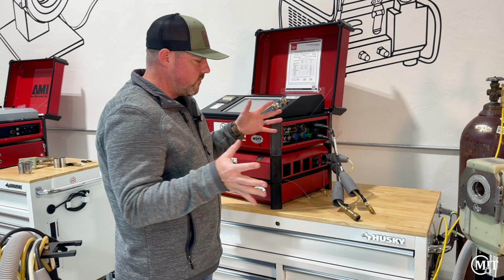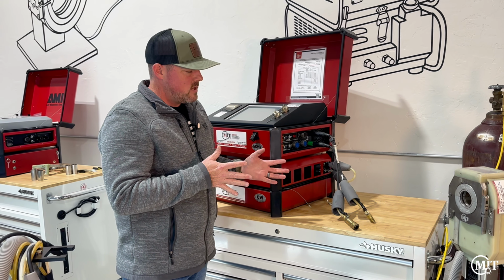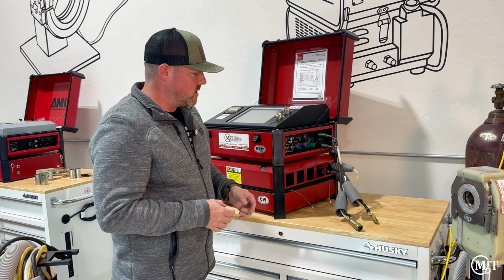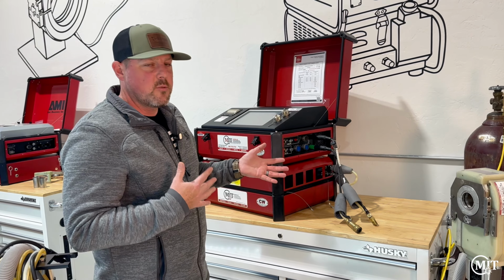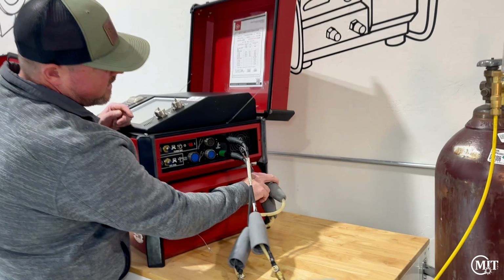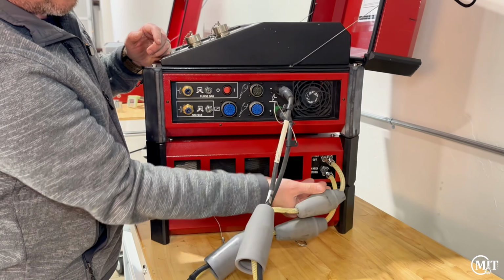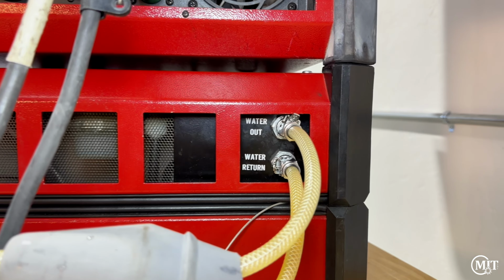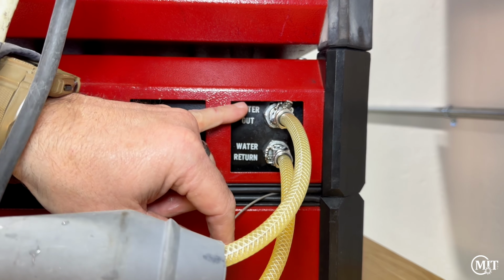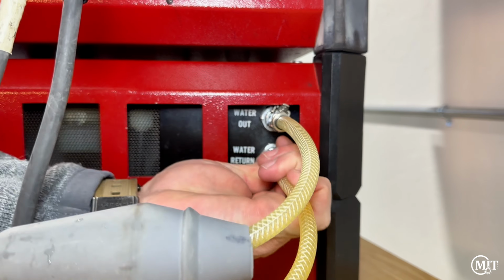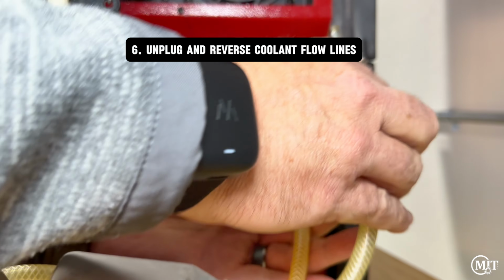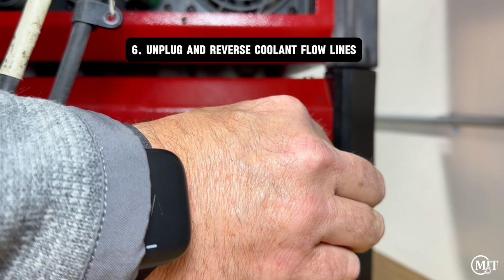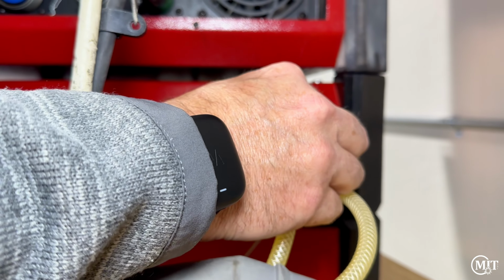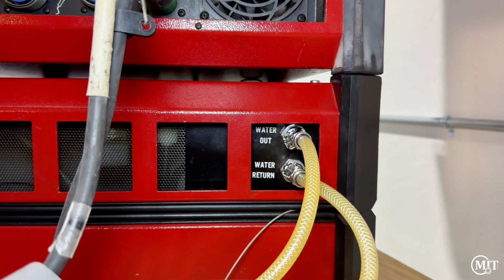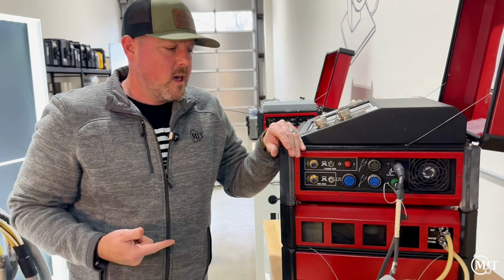So let's say we've connected everything and made sure it's completely seated as it should be. The next thing, if we still don't have coolant flow, we come over here to where your coolant lines are connected to your water cooler. These lines just have your return and your out. So we're going to unplug this, making sure to turn your cooler off whenever that happens, and we're just going to reverse them since they aren't male and female so they can go wherever. By reversing them, we've changed the direction of the water flow.